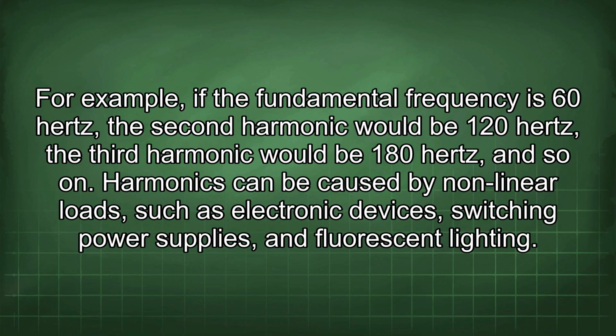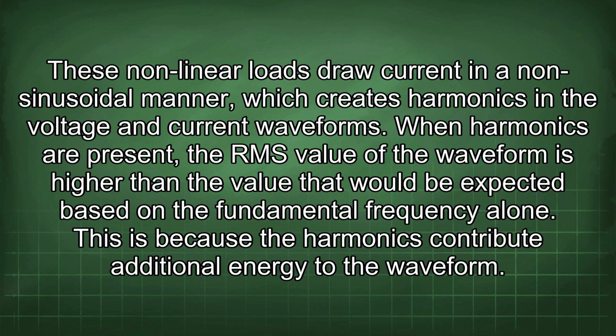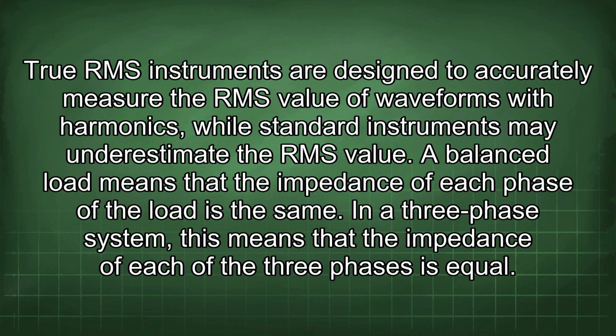Harmonics can be caused by nonlinear loads, such as electronic devices, switching power supplies, and fluorescent lighting. These nonlinear loads draw current in a non-sinusoidal manner, which creates harmonics in the voltage and current waveforms. When harmonics are present, the RMS value of the waveform is higher than the value that would be expected based on the fundamental frequency alone. This is because the harmonics contribute additional energy to the waveform.